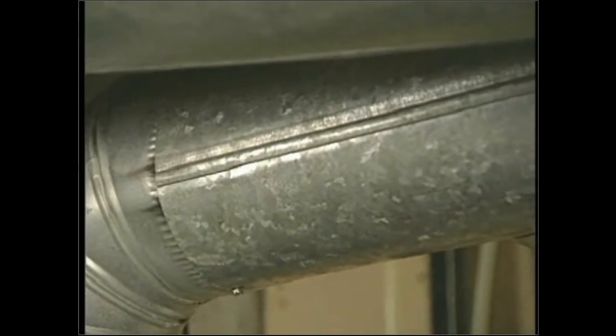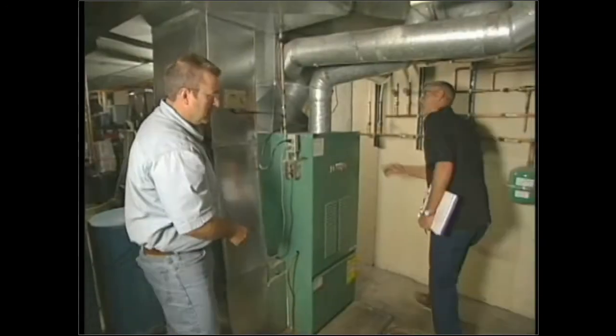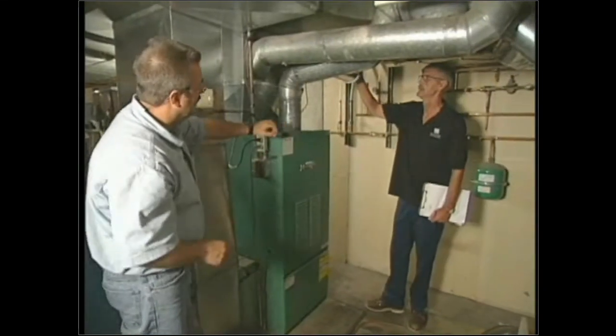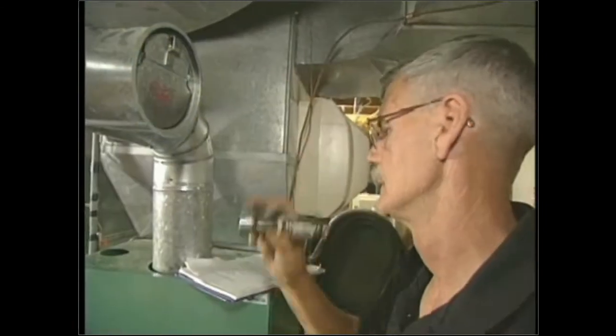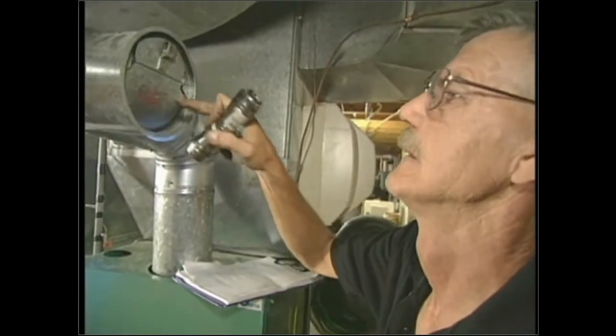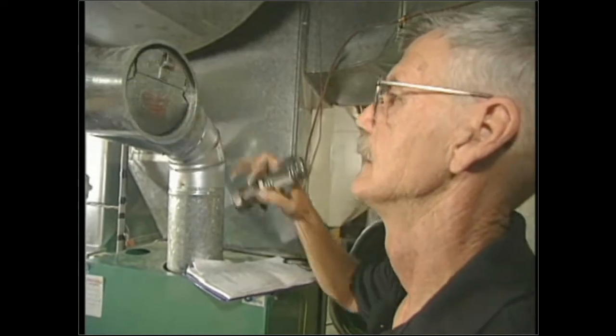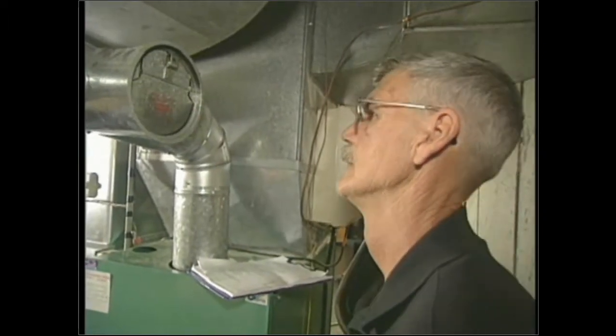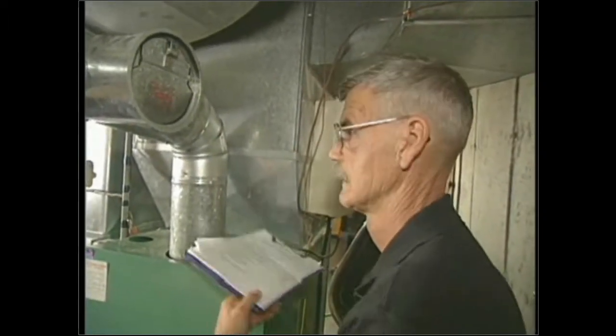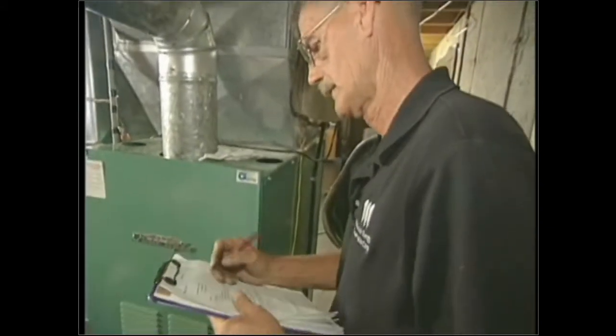And then another thing I'll do is I'll check the barometric control, which is located right here on this side. And this is what controls the overdraft of the fire. I want to check this to make sure that it's moving freely and clearly. There's no restrictions. It moves easily. Okay. If it isn't, I'll document it and have the technician come when he works on the furnace to tune it, to free it up and make sure it's working properly.